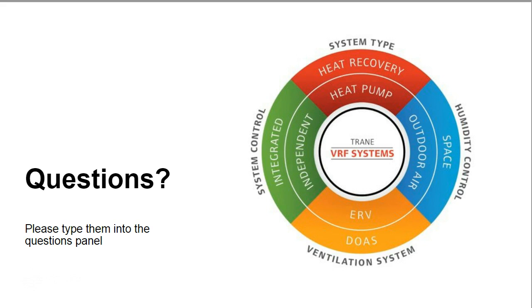So I would have to say that using terminal zone units on a different manufacturer's VRF system is not going to be compatible. The units might power on, but they won't communicate back with the outdoor unit. So I would have to say that that's not a smart decision to make.